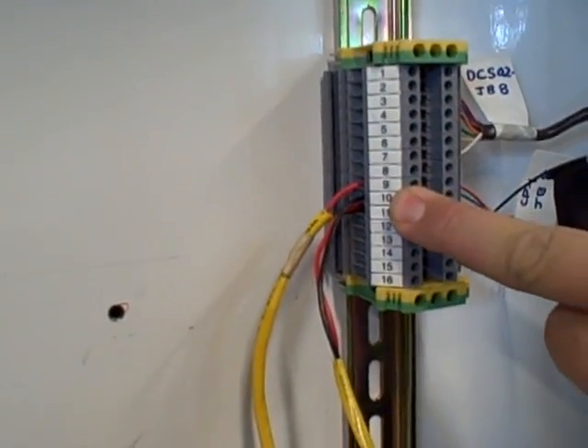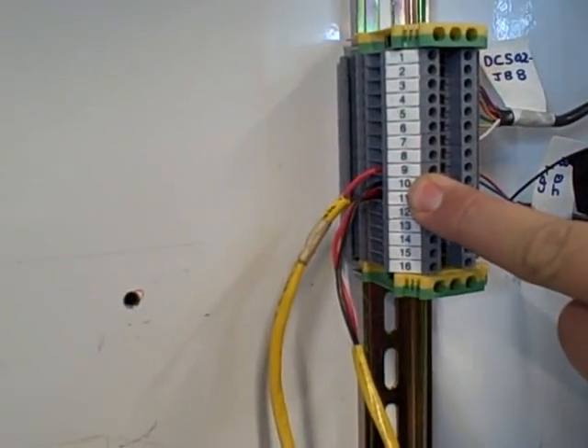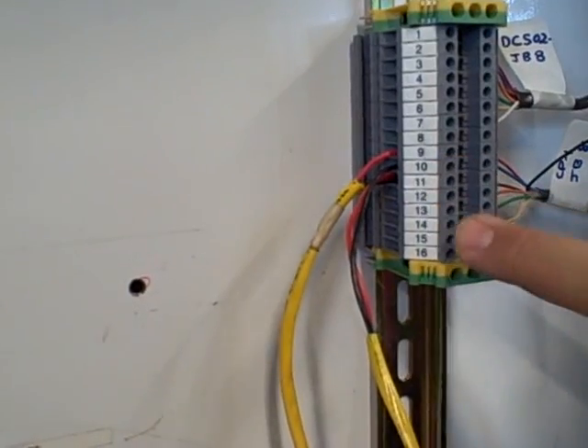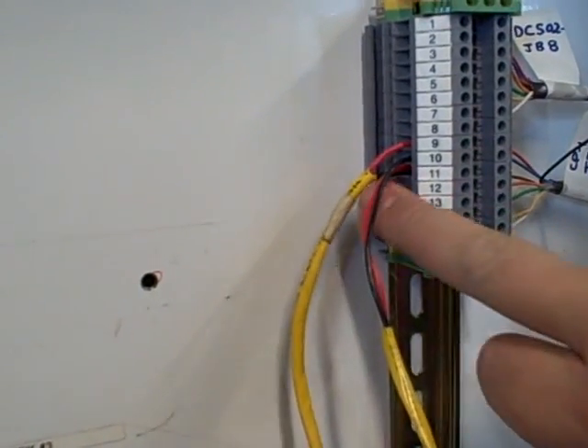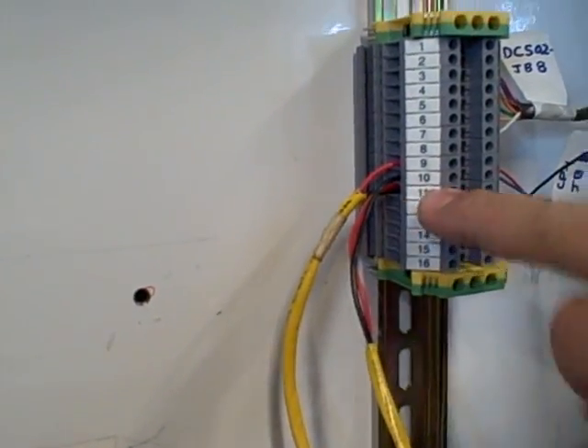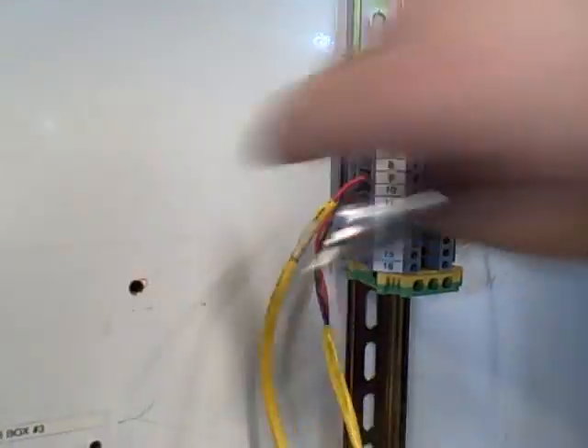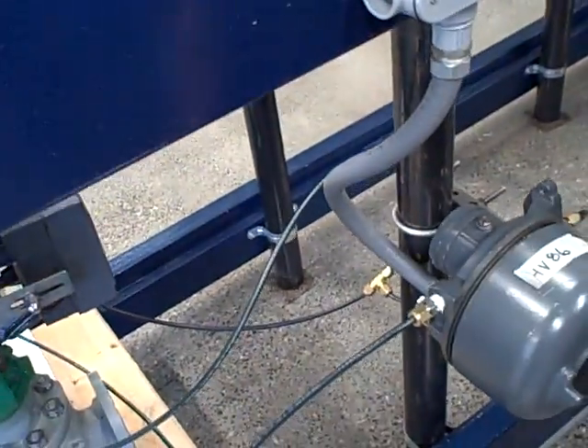And terminal number 9 is red. And then the black should be coming out of 11, which it is, which is coming out of 11. We tug on both. Good. Seem to be in good. They will follow through this opening here to this conduit. All right. That comes over here. It goes all the way over here to this I2P transducer.